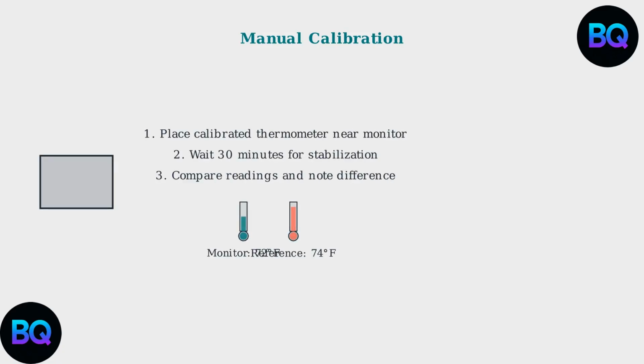For precise temperature monitoring, manually calibrate your sensor using a reliable digital thermometer as your reference standard. Place a calibrated digital thermometer near your monitor and wait 30 minutes for temperature stabilization. Compare the readings and note any differences. Apply the offset correction in your app settings if available. In this example, you would add 2 degrees to compensate for the difference.